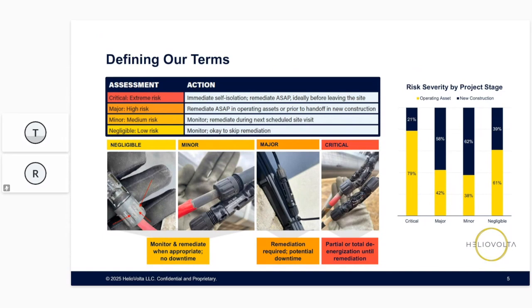Another thing to keep in mind is that the same general type of issue can actually present at different risk severities in the field. Let's use the example of improperly torqued connectors here. On the bottom part of this slide, under negligible, you can see an isolated instance of an over-torqued connector with signs of improper tooling—there are excessive marks on the back nut, indicating pliers were probably used to tighten it, not a proper torque wrench.